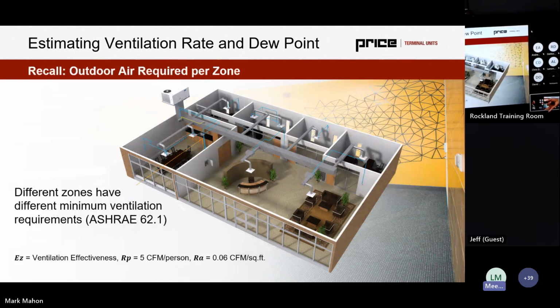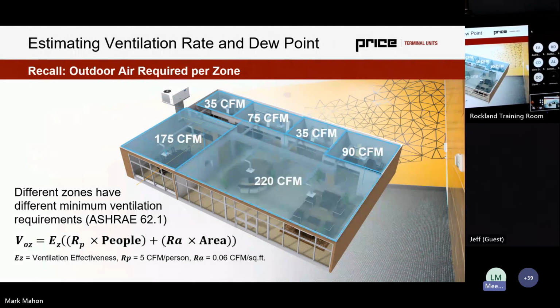So if we recall, we have our outdoor air required per zone. We already went through this. Each zone has a different minimum ventilation requirement per ASHRAE 62.1 based off of the number of people and the square footage, how well we mix the air within the space, and the type of space that we're actually constructing.